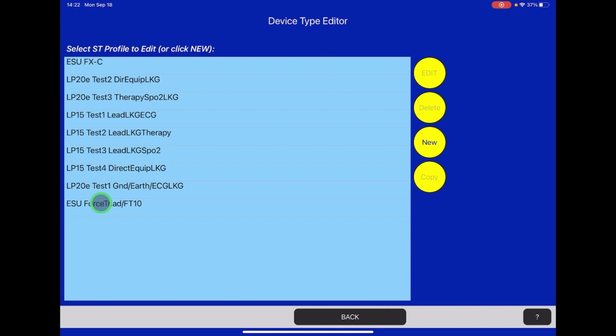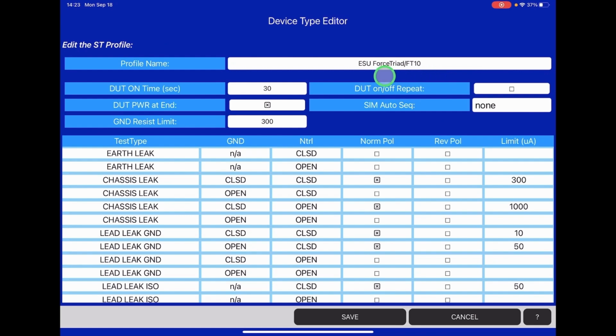For our purposes, we already created the FT10 procedure, but let's take a quick look at it and see what test we're going to perform. So you tap on Edit, and you can see at the very top here you have the name of the profile. We've already gone ahead and given it a name that would be easy for us to search and identify so we know what test we need to perform. Below that you have DUT on time, which is how long you want the test to perform before it advances to the next test. Because the ESU we're testing has a longer boot up time, we've gone ahead and set it for 30 seconds.